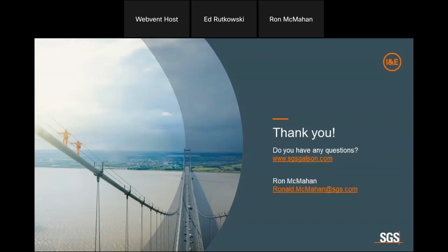So the unit actually has a built-in chamber in and of itself. It's literally like creating its own little chamber for the sensors. Typically, that chamber is open through, if you look at the Smart Sense unit, it's just got a cross on the front. And then you'll look down to the bottom right and you'll see the inlet for the particle sensor, which also exhausts air into the chamber. So when you block all that off and you put the gas into the chamber, it's literally like its own little mini chamber.